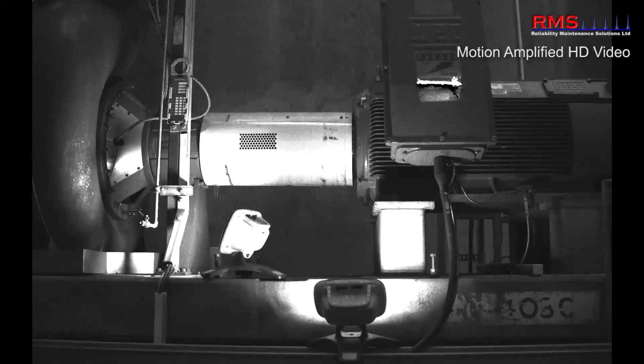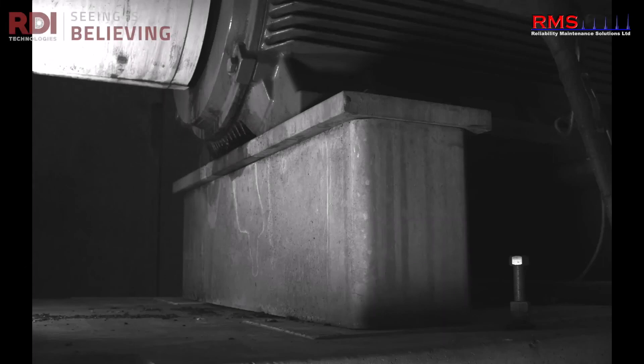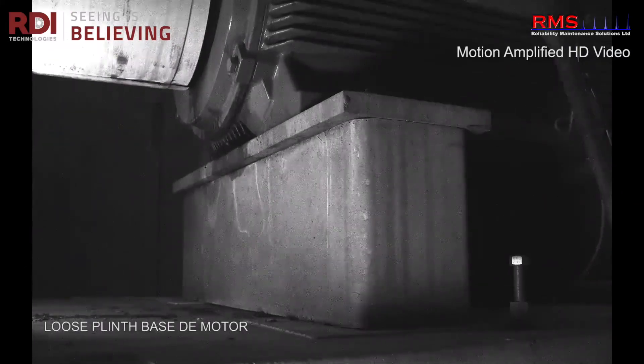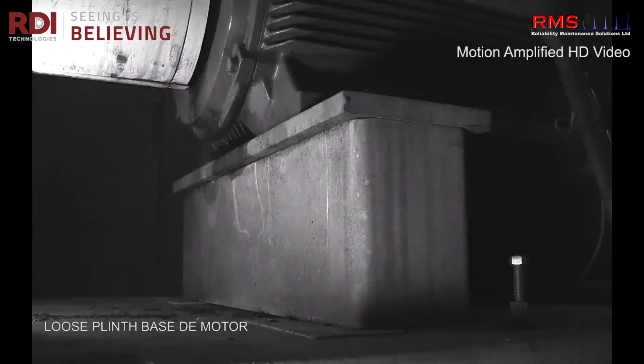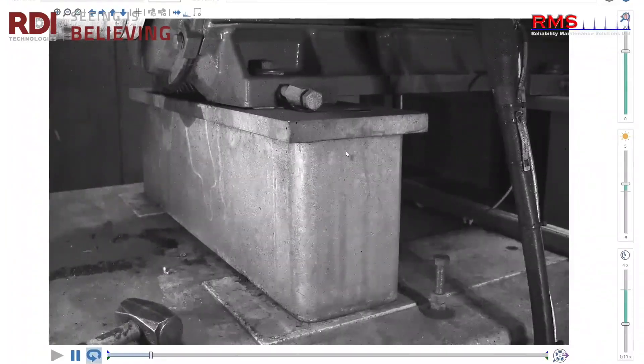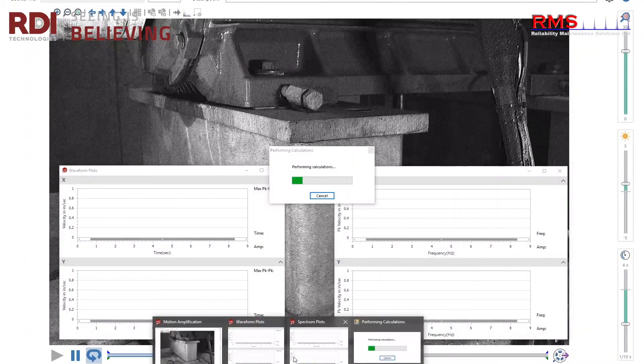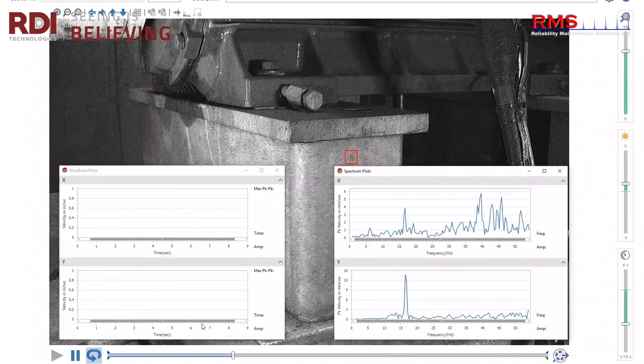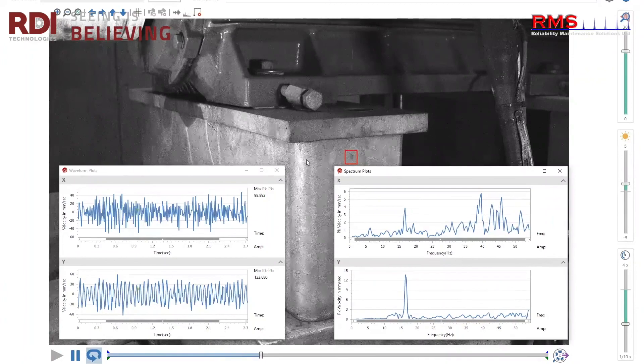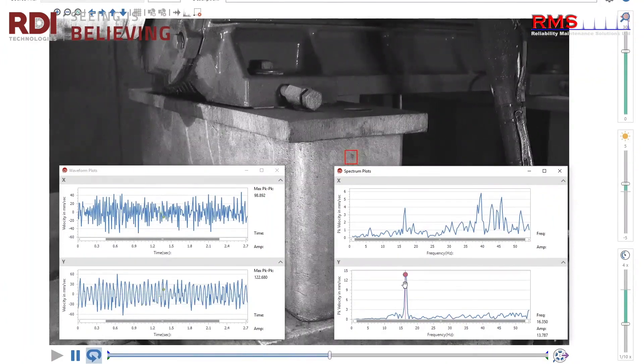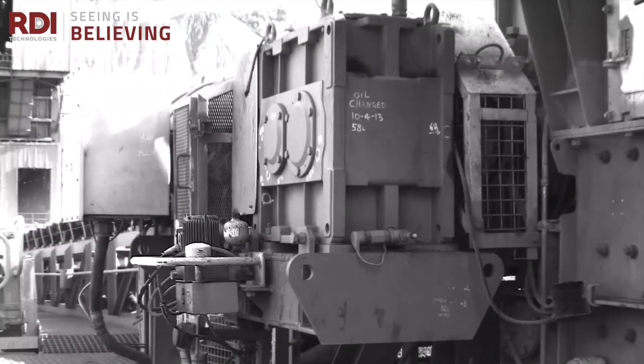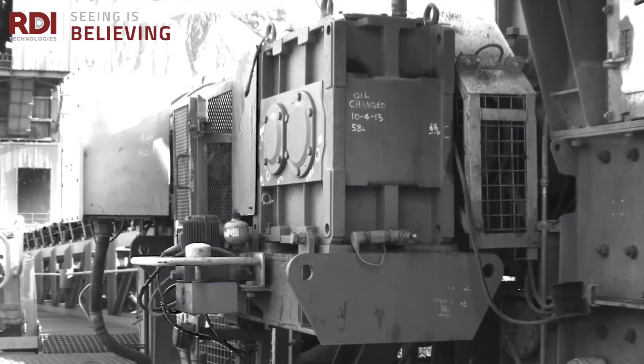Traditional vibration technologies and monitoring sensors cover a lot of different assets, but there are plenty of important pieces of the puzzle that are left unmonitored, such as process lines, bases, and foundational elements that are often the culprits of hard-to-solve vibration problems. Because motion amplification is completely non-contact, it is able to easily see and measure these elements that are difficult for traditional sensors to measure. Motion amplification is a cheaper per-point measurement that makes comprehensive analysis easier and broadens the coverage you can provide to your entire facility.